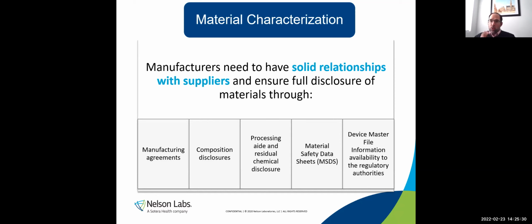But along with that, you also need to know what possible residuals might be on their materials. Like we talked about before, it's not just about the material, it's about the residuals. And they may tell you it's silicone, and that's great. We know silicone's pretty safe, but what are they using during their manufacturing process? Are they cleaning it? Are they using a detergent that's cleaning? Things like that. We need to know what kind of residuals could be on that material that now are on your device.